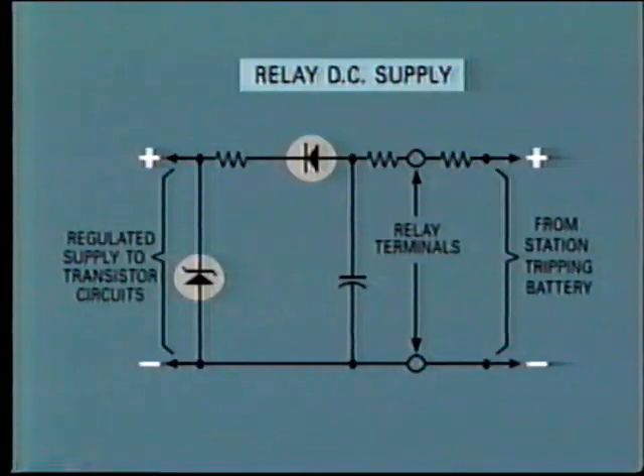Now, let's take a look at static relay power supplies. Most transistor circuits work on a specific DC supply voltage between 12 to 30 volts. This can be provided from the station battery or local tripping battery. A dropping resistor lowers the voltage to the relay's terminals to the desired level.